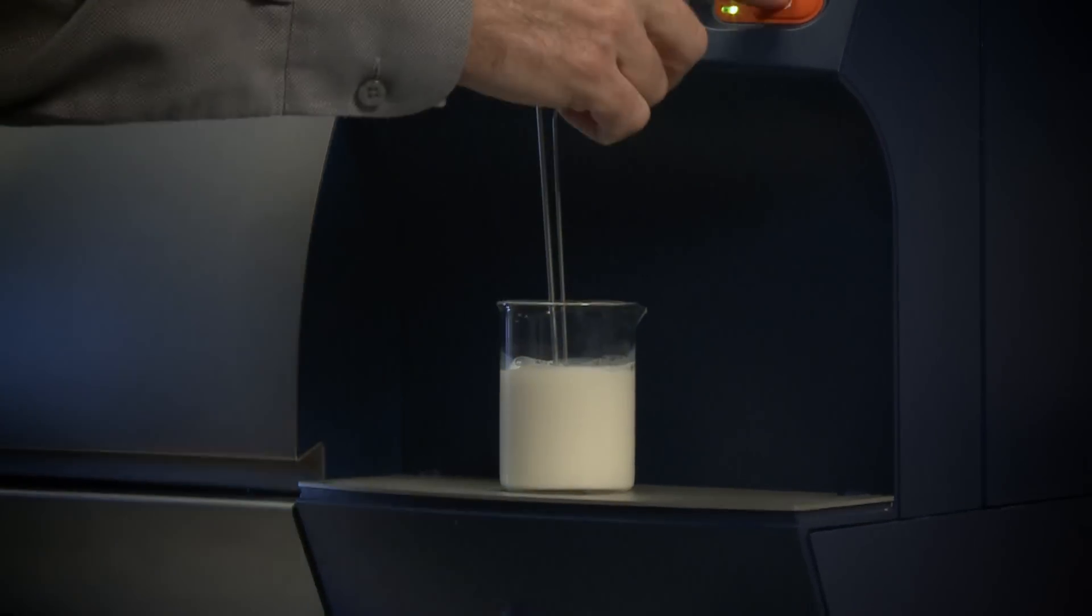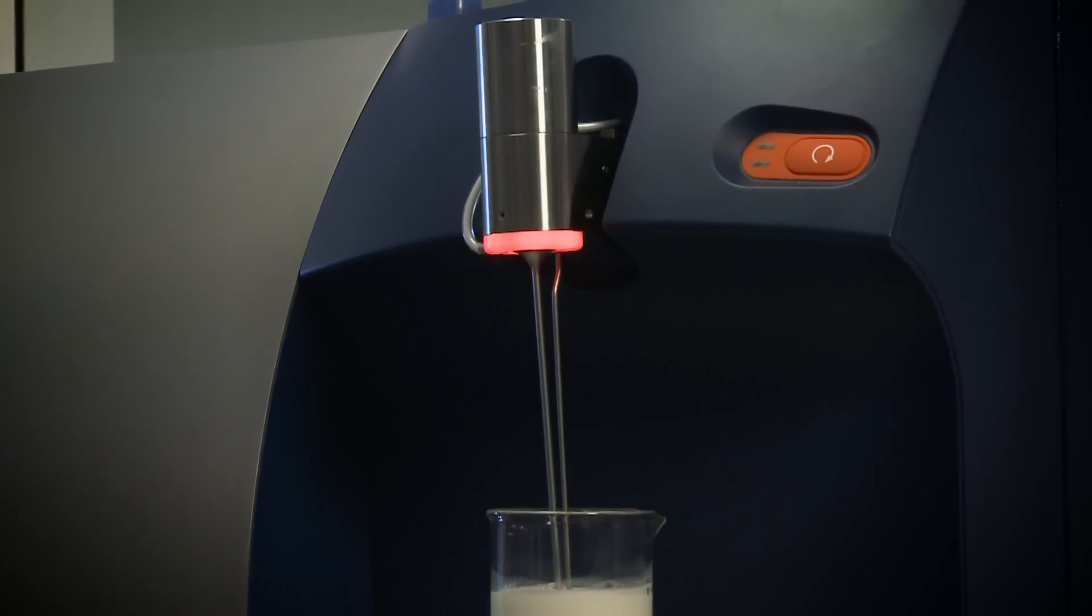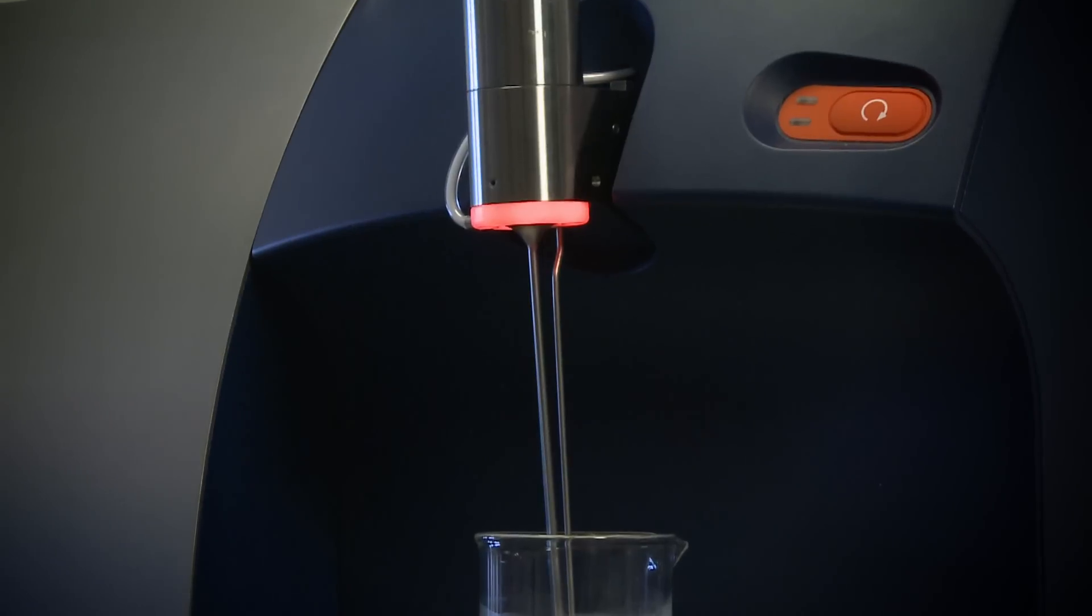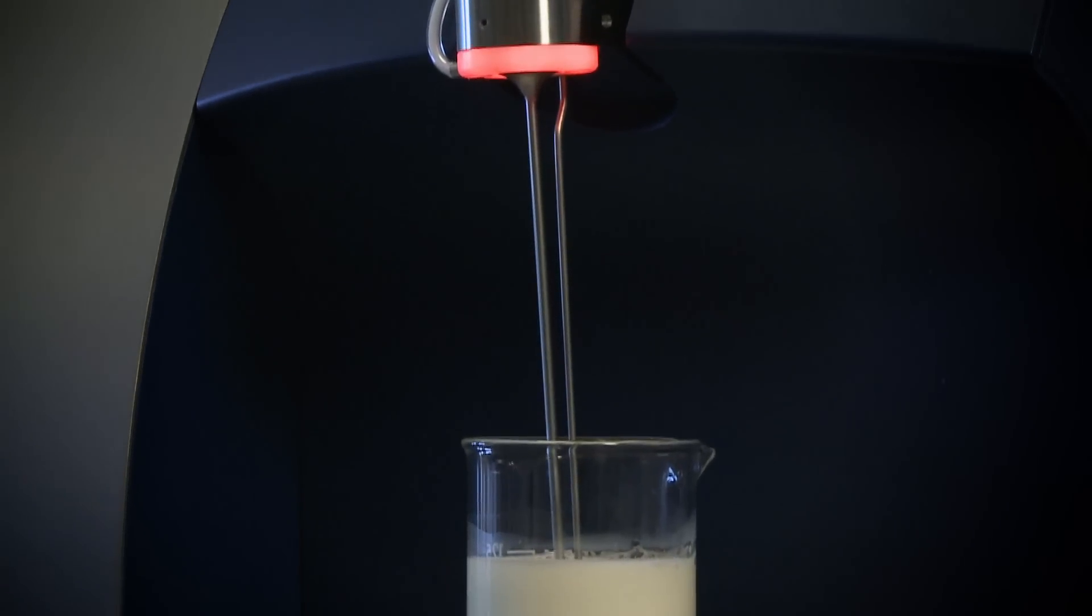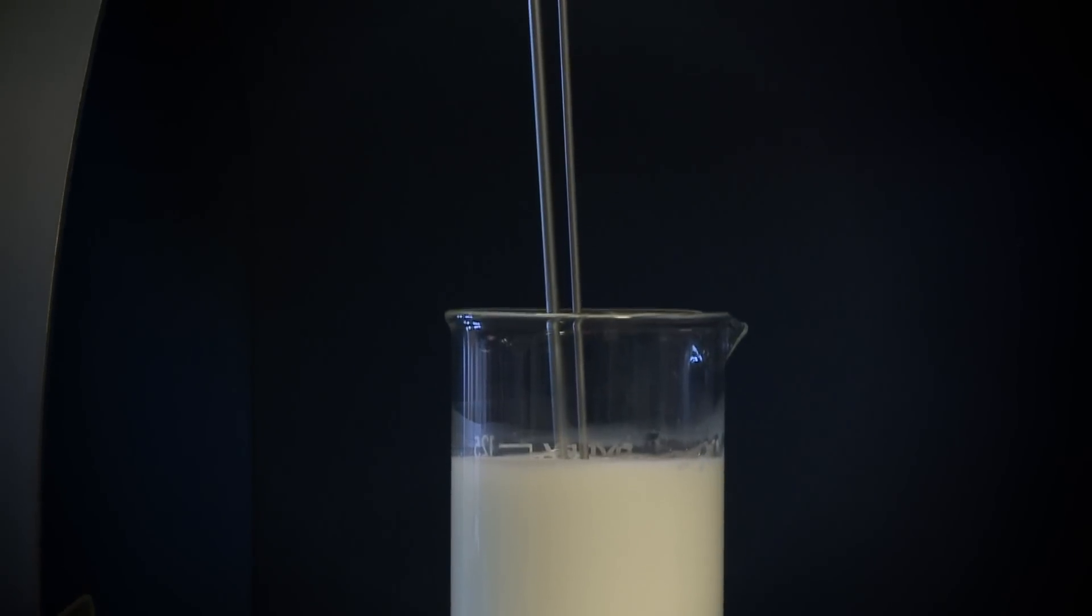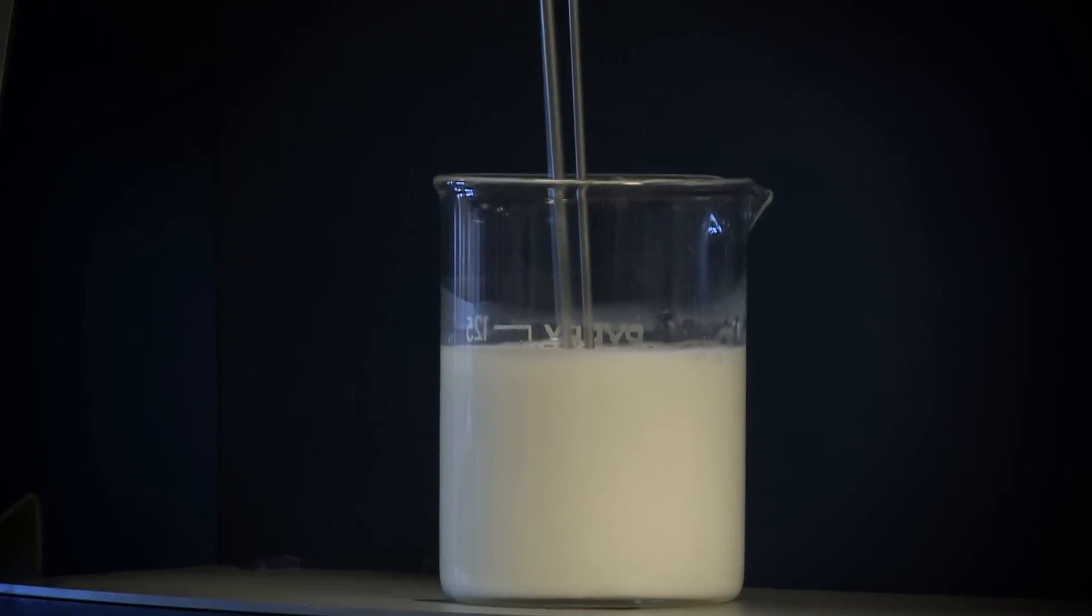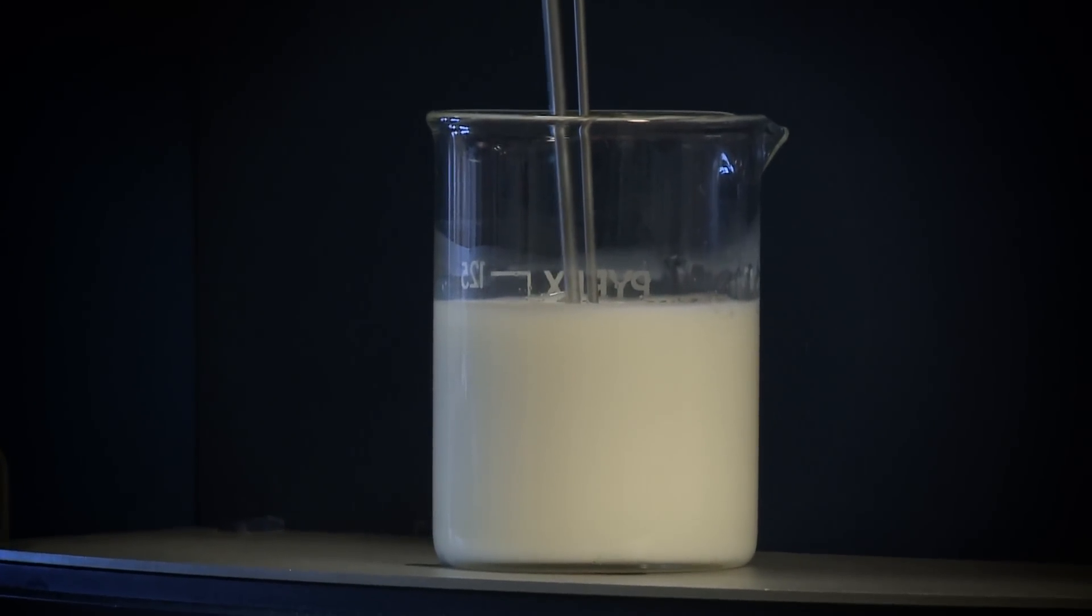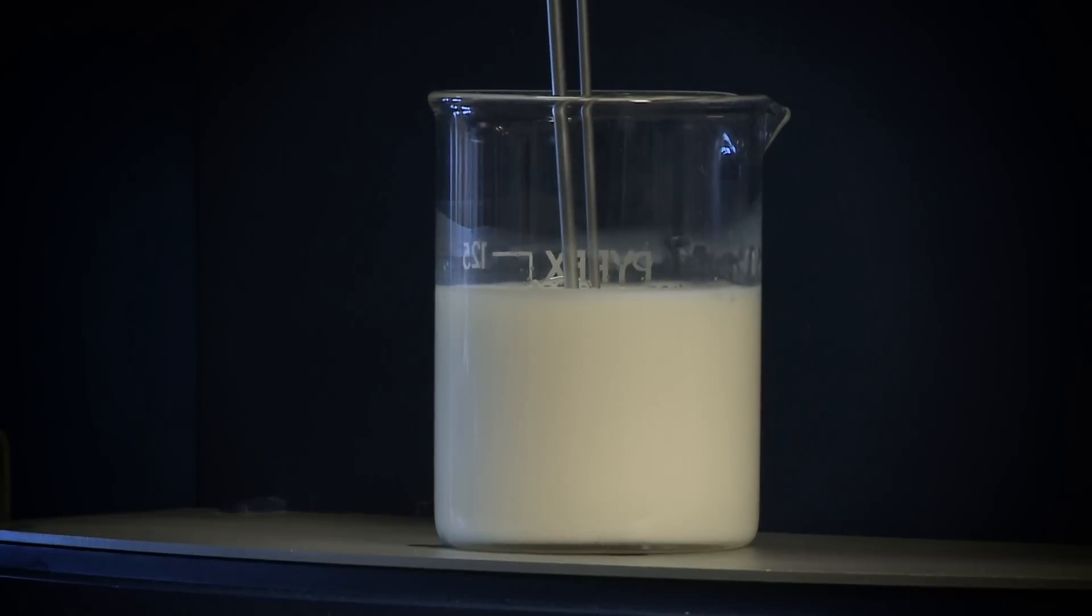With a modern instrument, we have a very modern optical bench which develops a full spectrum. The full infrared spectrum is essentially gathered in at one time. That's why you can run a sample, and at one instant the full infrared spectrum is collected.